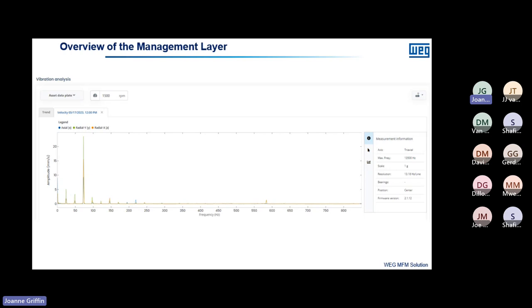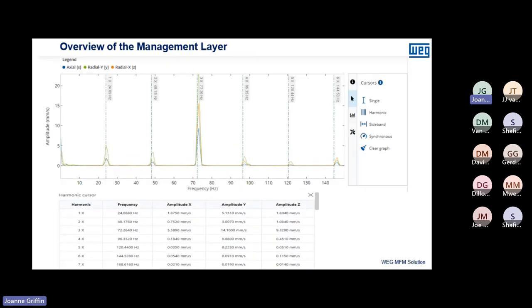I zoomed onto one of the spikes and placed the harmonic cursor on the fundamental frequency — the frequency at which the machine is rated. This reveals all the remaining harmonics — approximately 10 harmonics. Looking at the table below, the amplitudes of vibration at all harmonics are extremely high. That is exactly why this machine is in critical mode — the vibrations at these harmonics are very high.